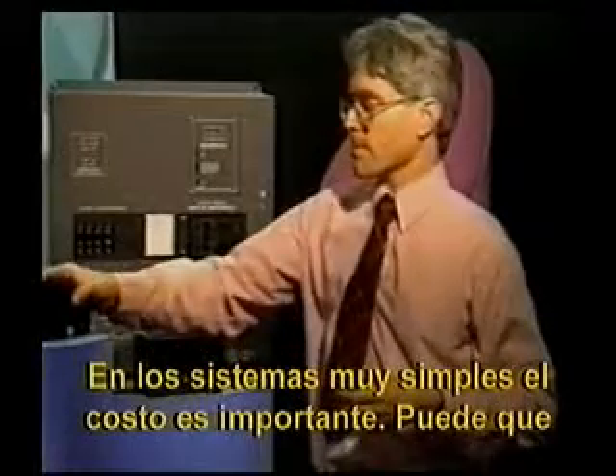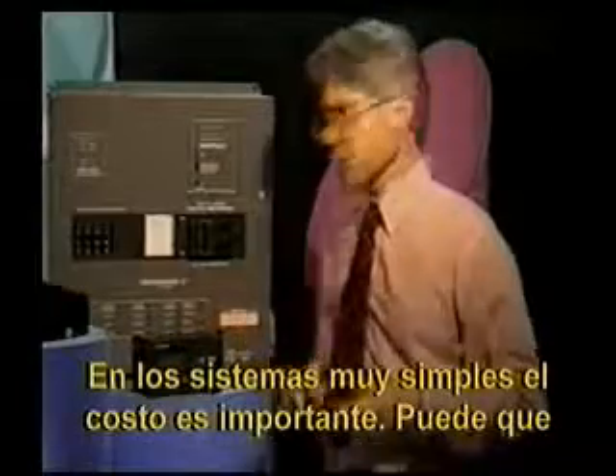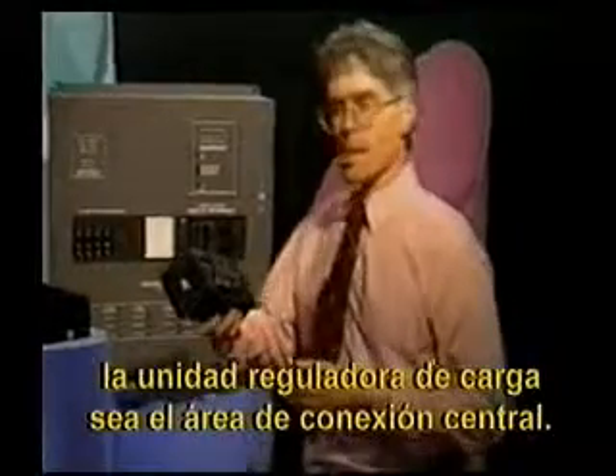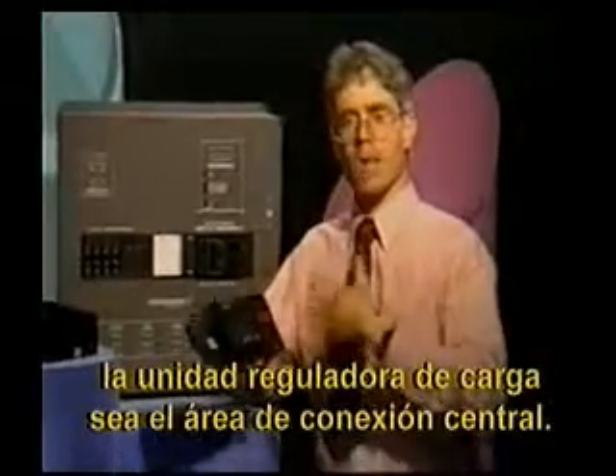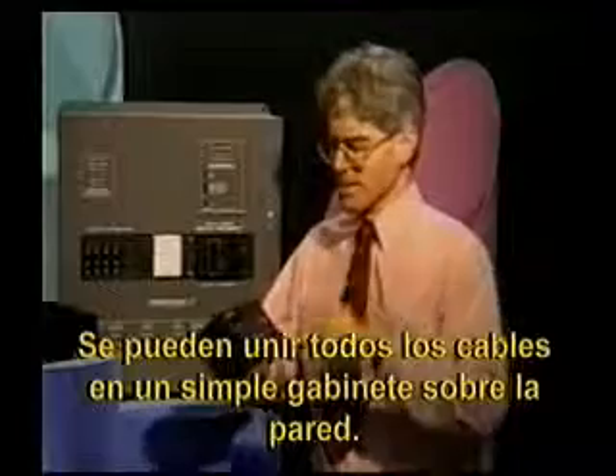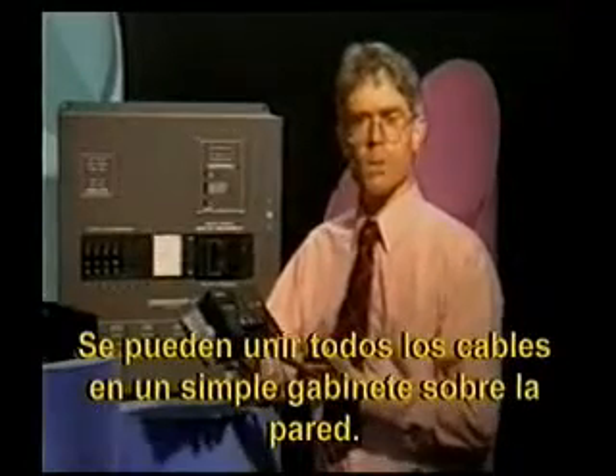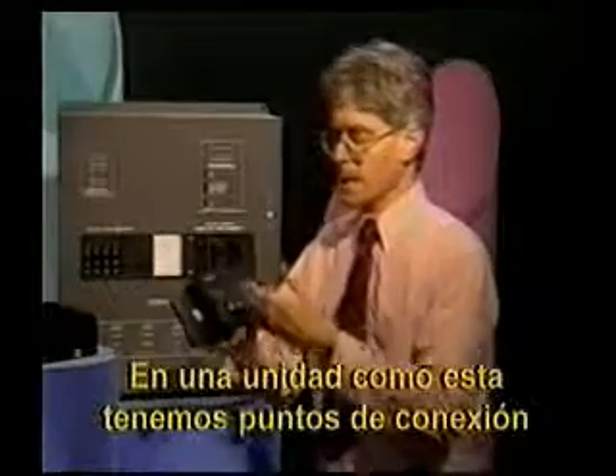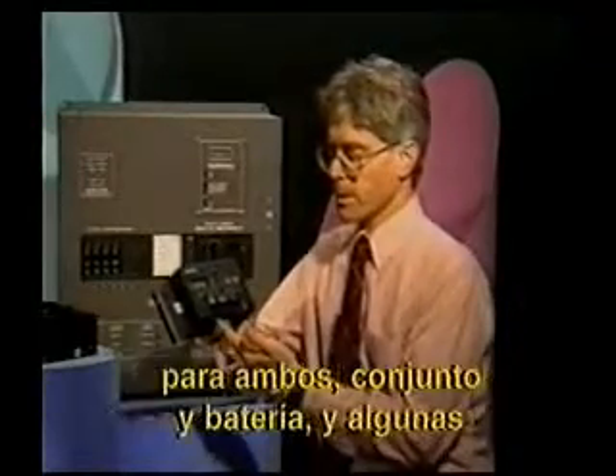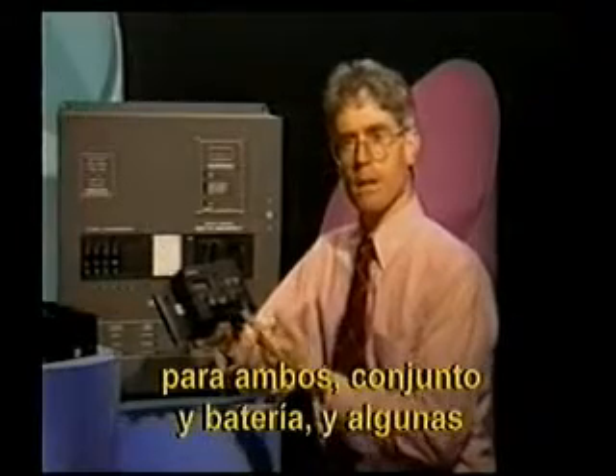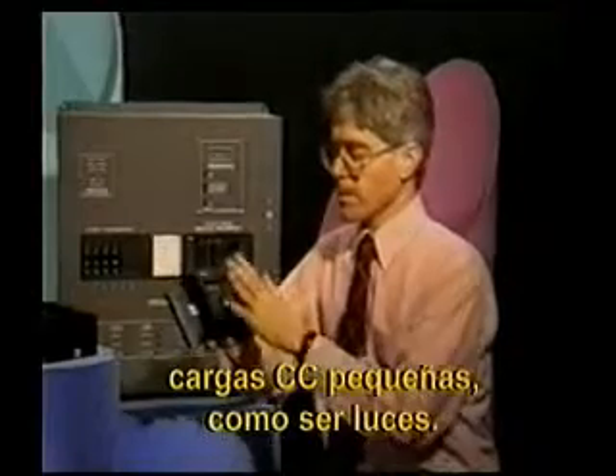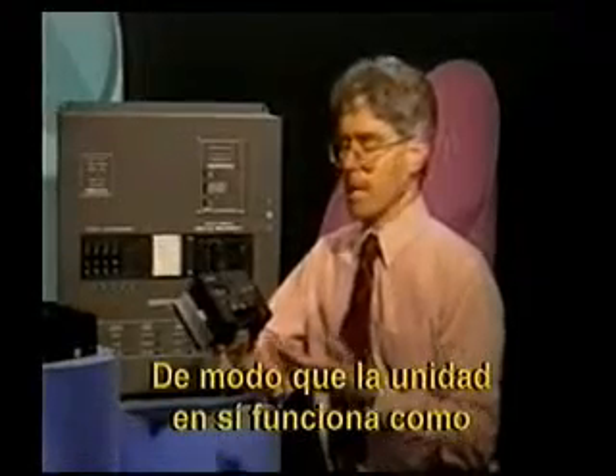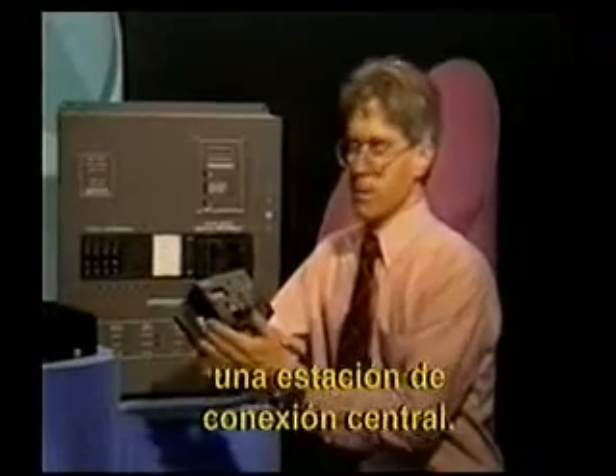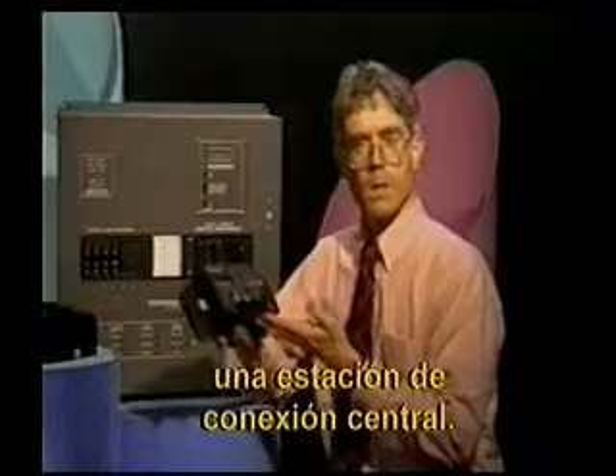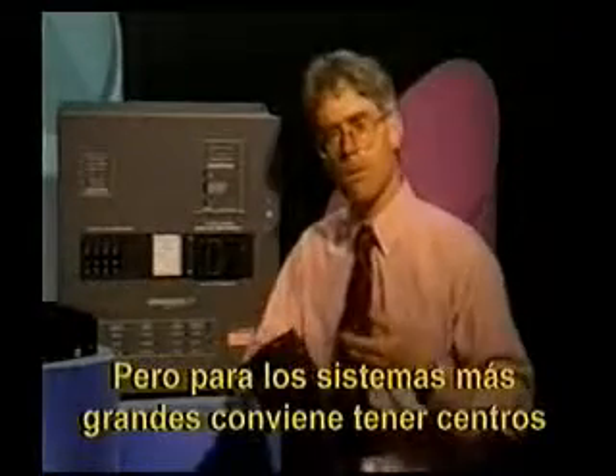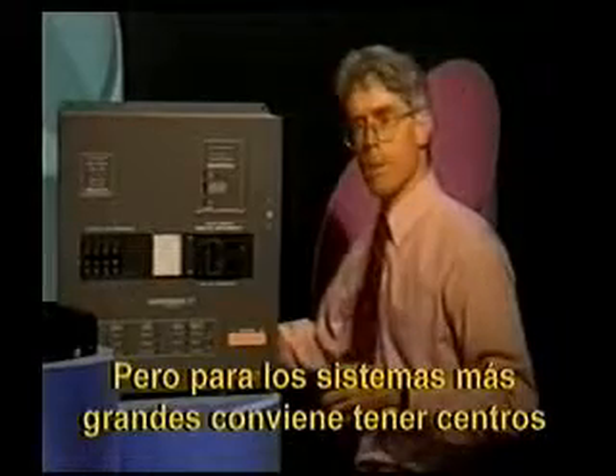In many cases, you might be dealing with very simple systems. Cost is important. We might have the charge regulator unit act as our central wiring area for a small cabin system where we can simply bring all of the wires into one simple unit that might be mounted on the wall. In a unit like this, we have connection points for both the array wiring, the battery wiring, and some small DC loads, maybe some lights. So the unit itself acts as a central wiring station. It might include, as in this case, array fusing and battery fusing internally, so the safety units are actually built in. But for larger systems, I think you're going to want to consider power centers.